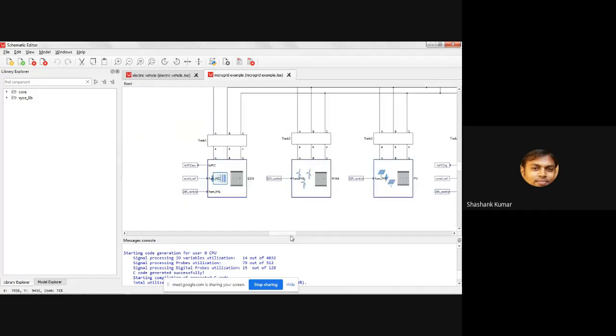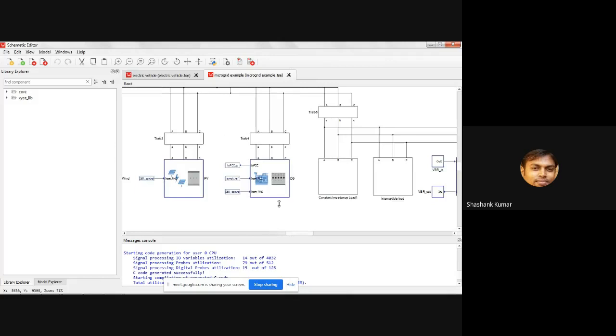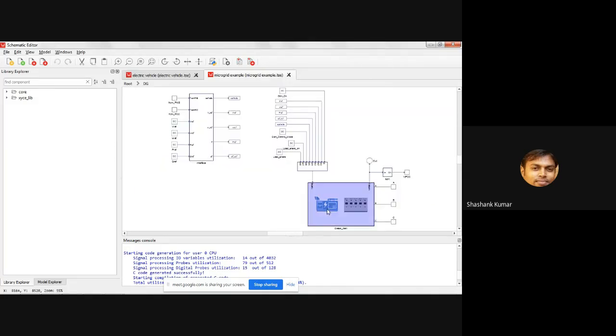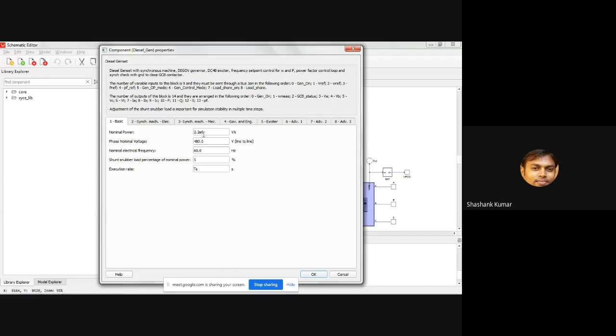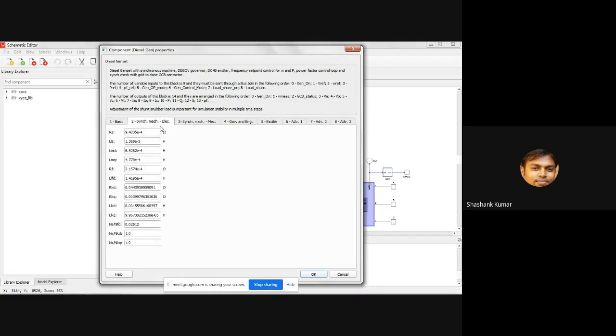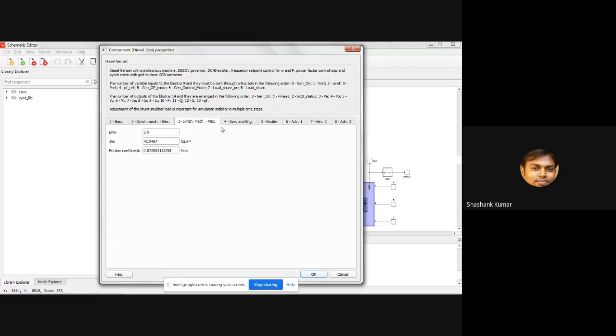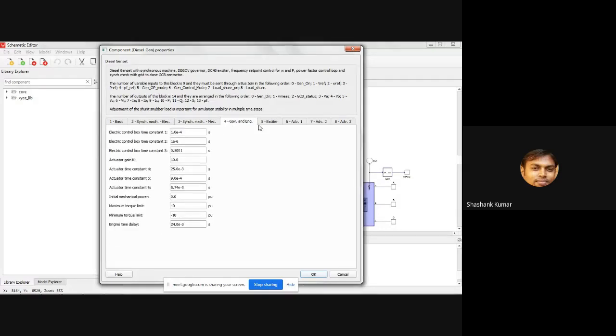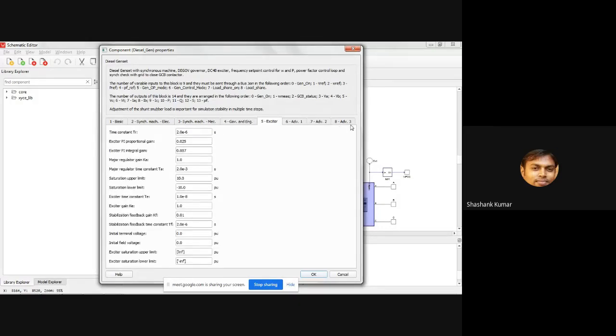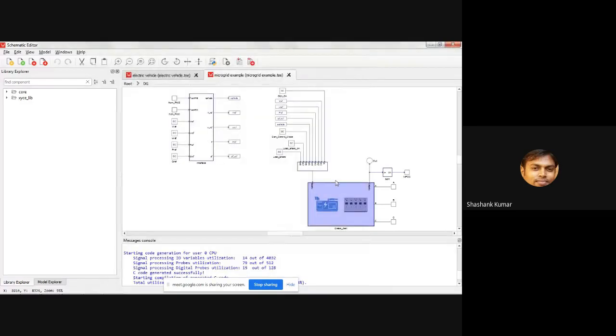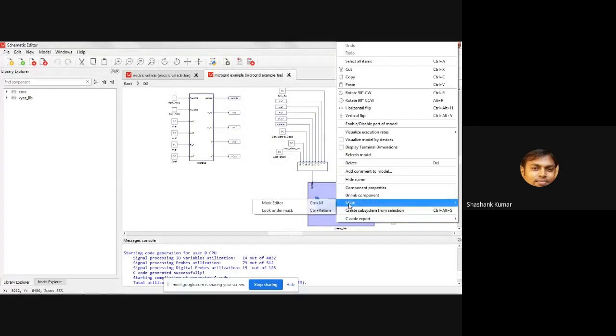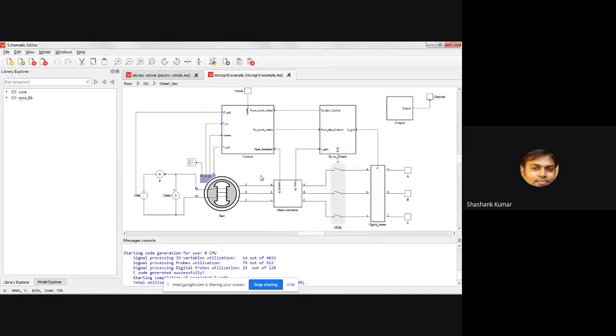Okay, and the last one is the DG plant. If you see inside the structure of this one, it has a rating of 2.2 MVA with 480 volt line to line voltage and 60 hertz frequency. These are the synchronous machine electrical parameters, synchronous machine mechanical parameters, governor and engine parameters, exciter parameters, and the rest is controller parameters.